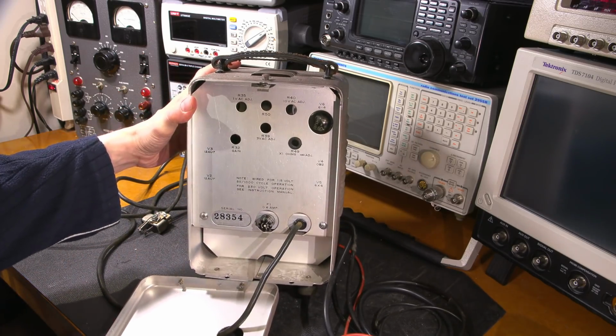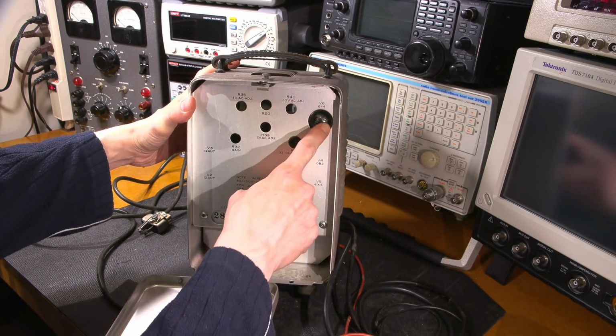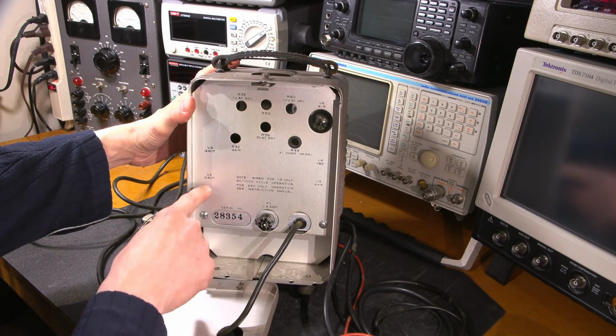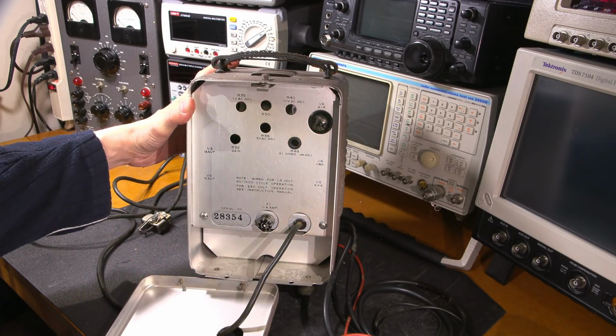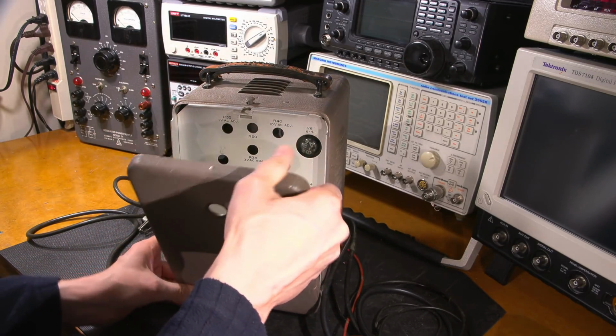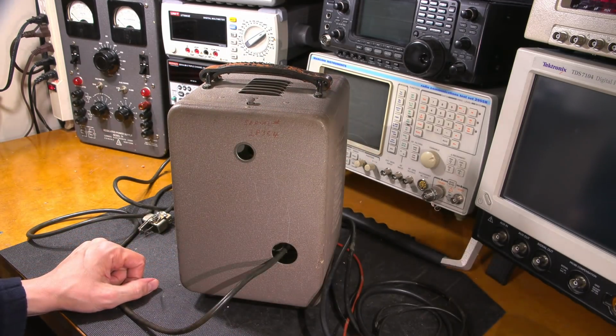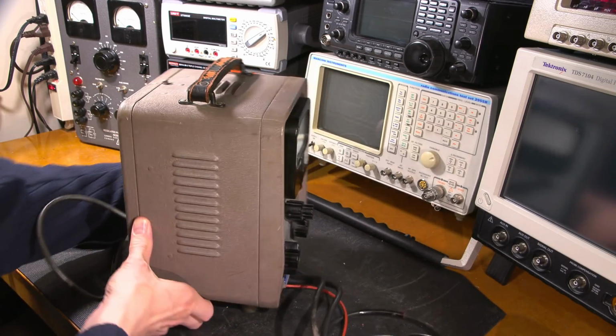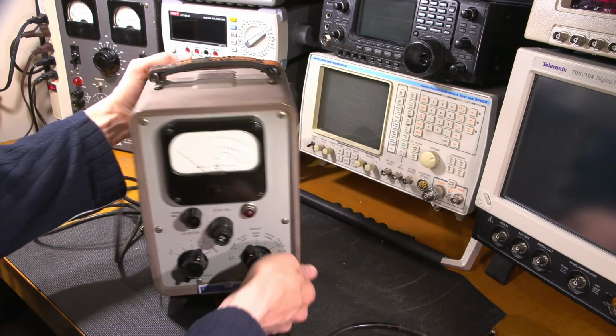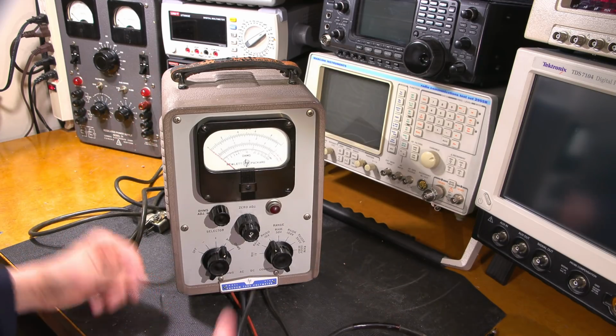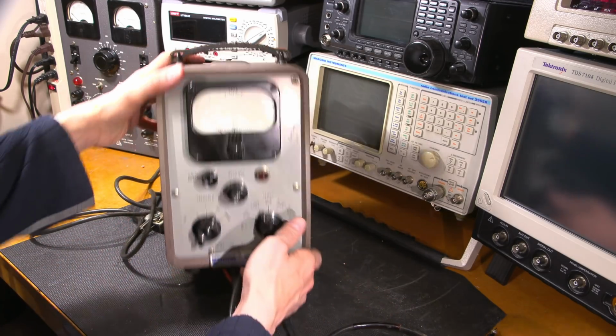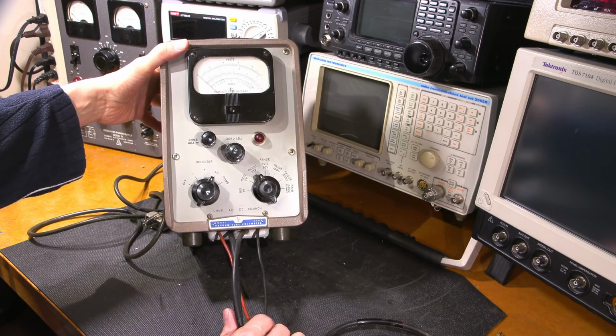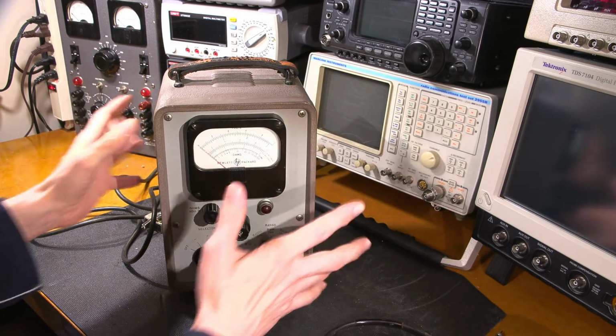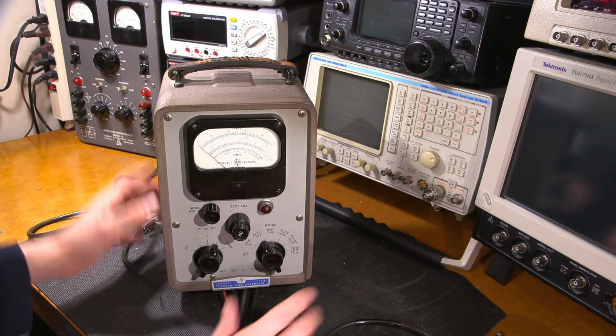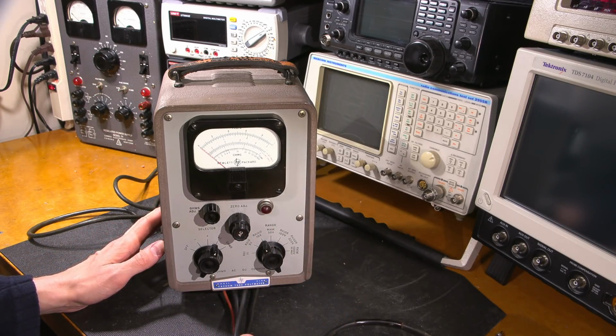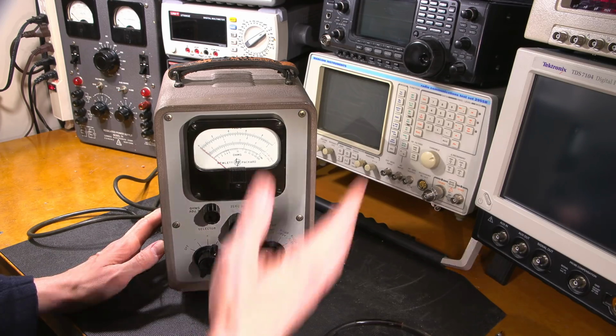So all the usual adjustments that you need to calibrate the unit. You see a tube right here, and they've listed the tubes right here on the outside, so they're behind this. So Hewlett-Packard made this relatively easy to service, which is very, very nice. So there are a lot of perks about this VTVM, aside from being very, very accurate. So great meter to own. If you ever have the chance to own an HP 410B, I would say jump on it. If you need a VTVM, this is the thing to have.